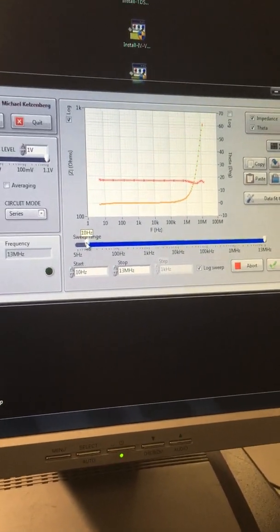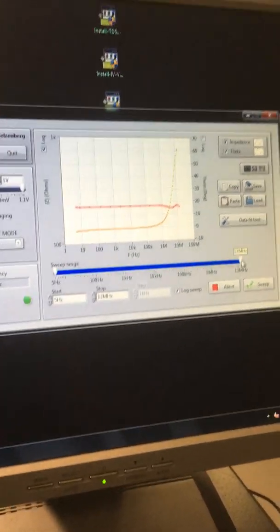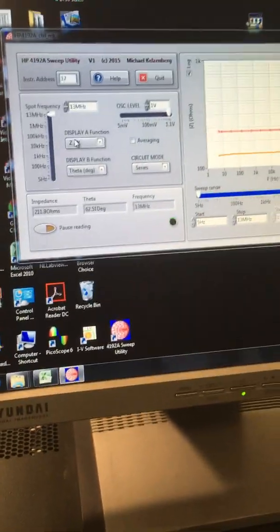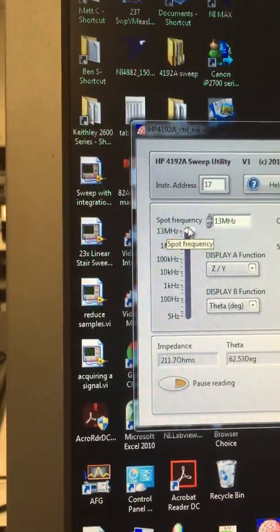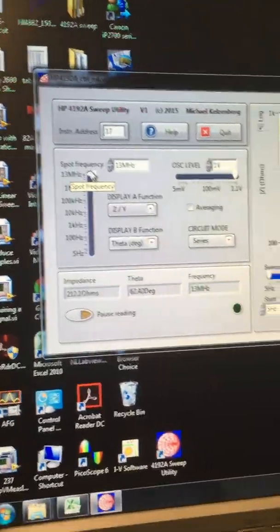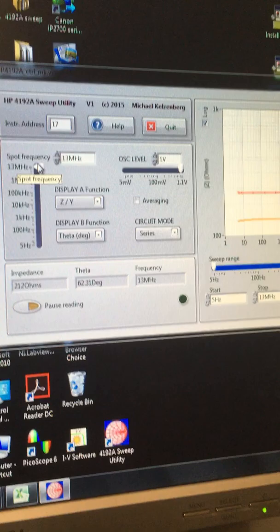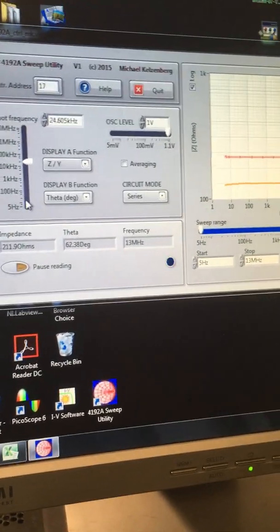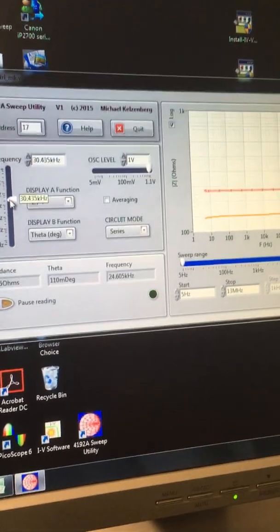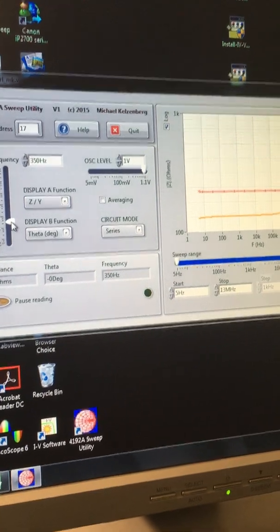So I always just do the full range from 5 Hertz to 13 megahertz. This is a spot frequency measurement, so this is just telling you what the impedance is at a particular frequency. You can change that and get an instantaneous measure. That's basically just sweeping down this graph here.